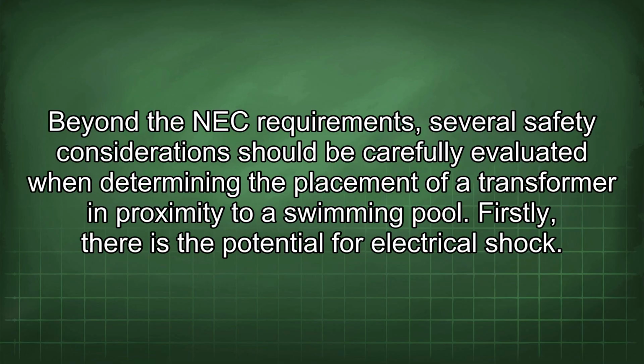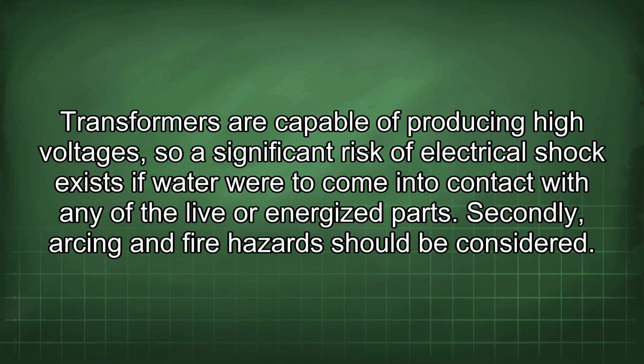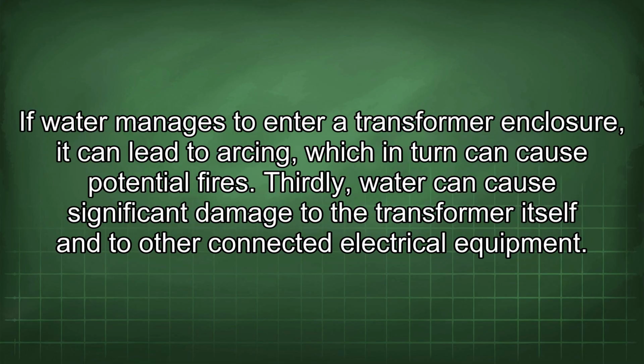Beyond the NEC requirements, several safety considerations should be carefully evaluated when determining the placement of a transformer in proximity to a swimming pool. Firstly, there is the potential for electrical shock. Transformers are capable of producing high voltages, so a significant risk of electrical shock exists if water were to come into contact with any of the live or energized parts. Secondly, arcing and fire hazards should be considered. If water manages to enter a transformer enclosure, it can lead to arcing, which in turn can cause potential fires. Thirdly, water can cause significant damage to the transformer itself and to other connected electrical equipment.